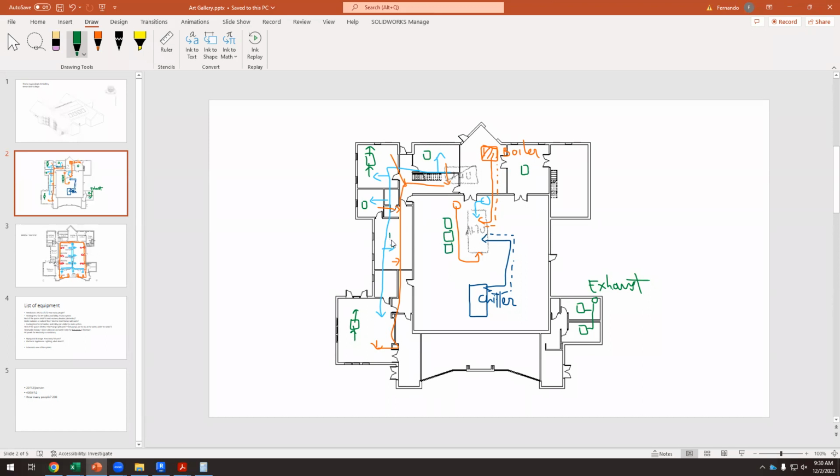1, 2, put everything on one here. 1, 2, 3, 4, 5, 6. So I will need 6 heat pumps here. And those heat pumps connected to the split systems can give me, if I need, most of the days I can get by with the heat recovery here and I have ventilation. But if I request some more heating or some more cooling, I can use the heat pumps with the splits. I think that would be the best solution.